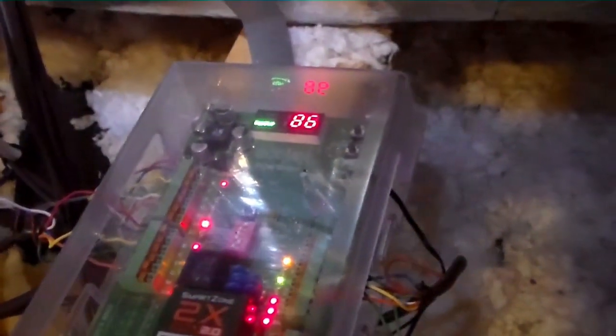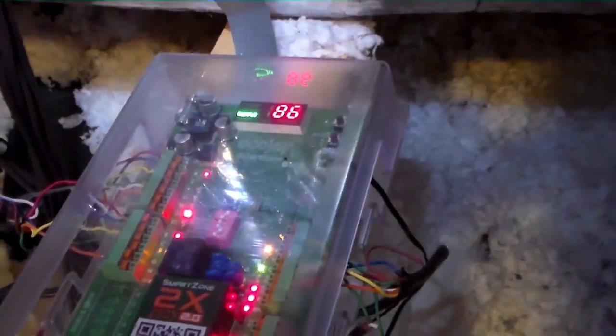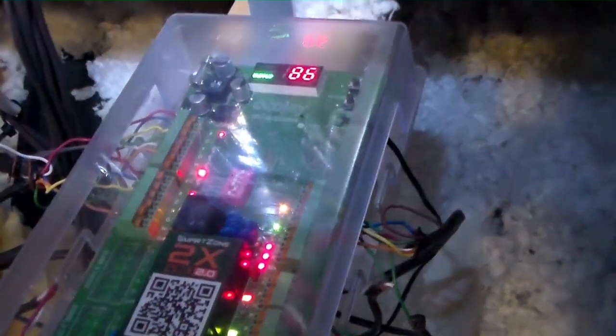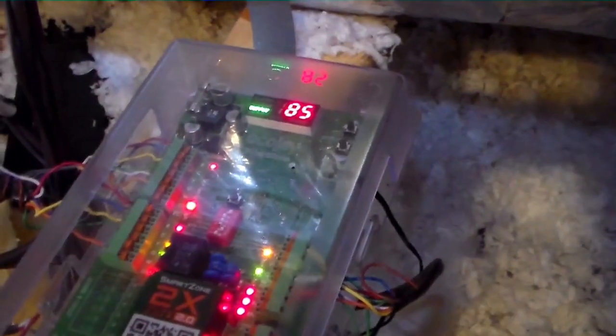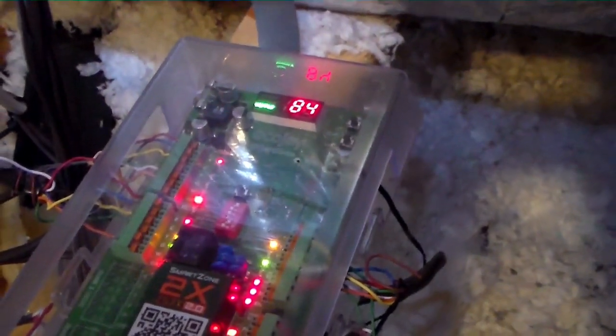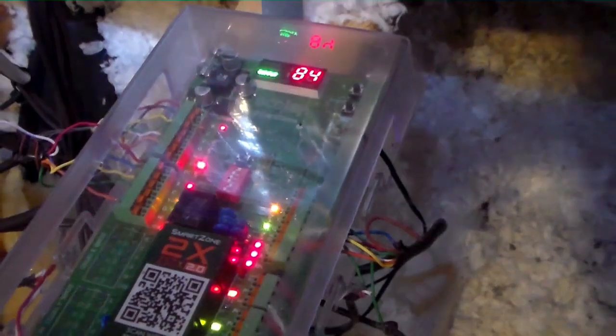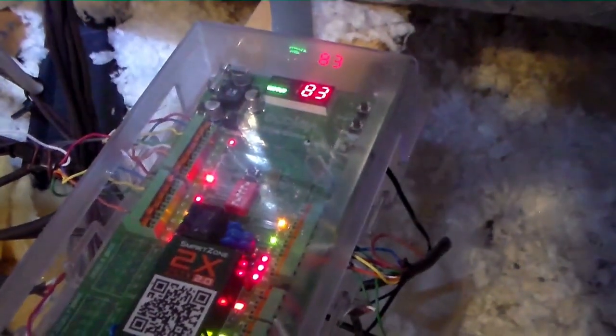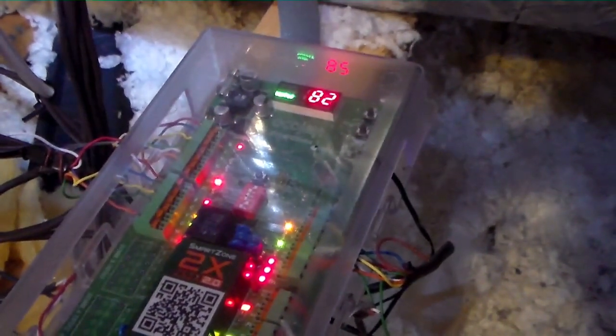If you listen, guys, you can start to hear the refrigerant traveling through the lines, which is good. Our temperature is 87 starting out. It'll start dropping when it senses the supply cooling off on our sensor, which is right here. So we should start dropping to 85 and run about 10-15 minutes, and it should settle out to the correct supply temperature. We'll let her roll for a minute and see how she does.